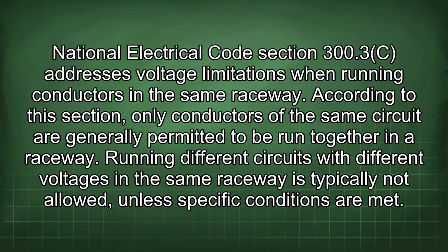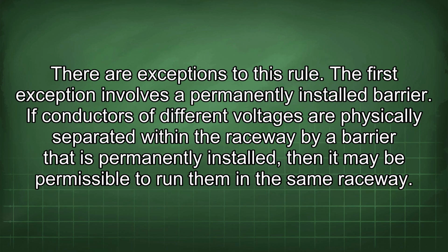National Electrical Code Section 300.3(C) addresses voltage limitations when running conductors in the same raceway. According to this section, only conductors of the same circuit are generally permitted to be run together in a raceway. Running different circuits with different voltages in the same raceway is typically not allowed unless specific conditions are met. There are exceptions to this rule.